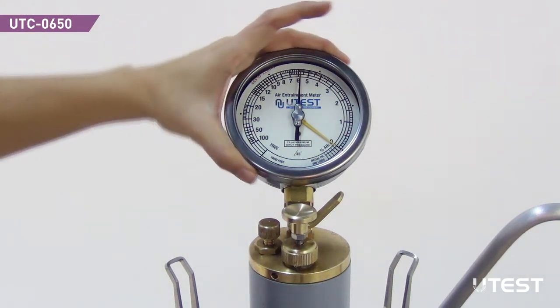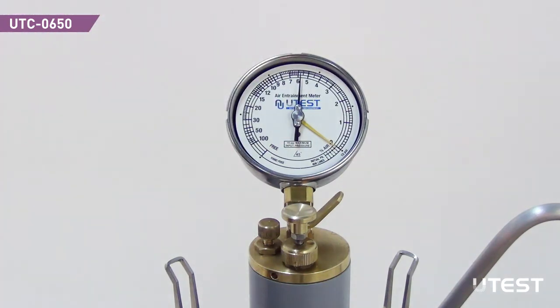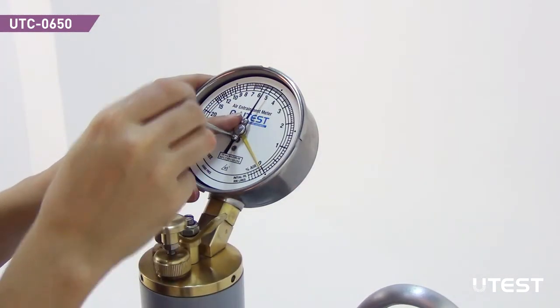If it is not, remove the safety glass on the pressure gauge and adjust the gauge hand by loosening the nut.